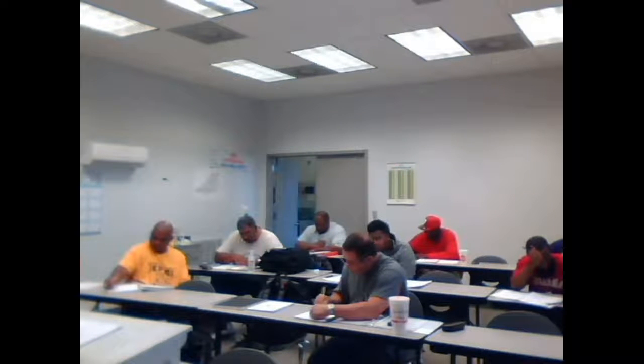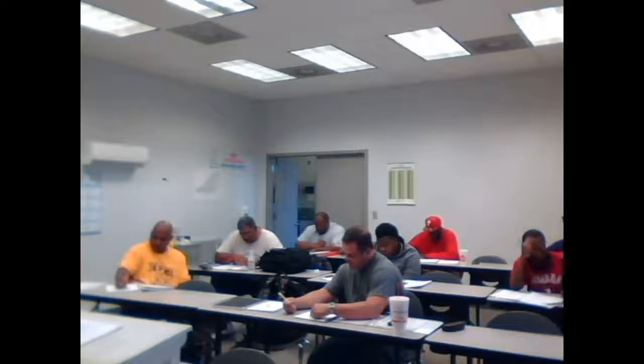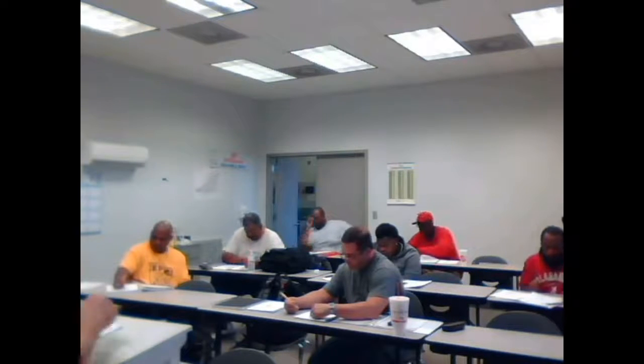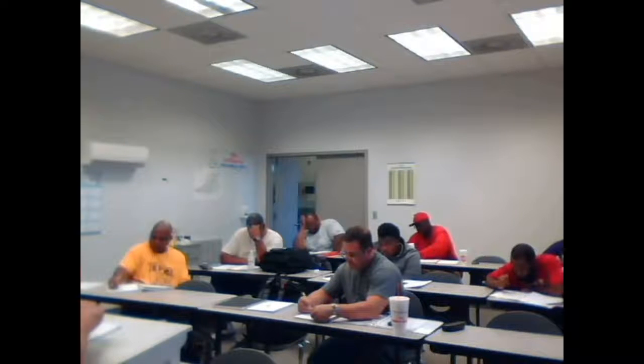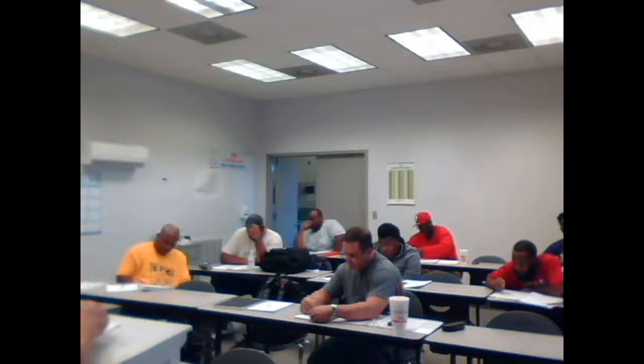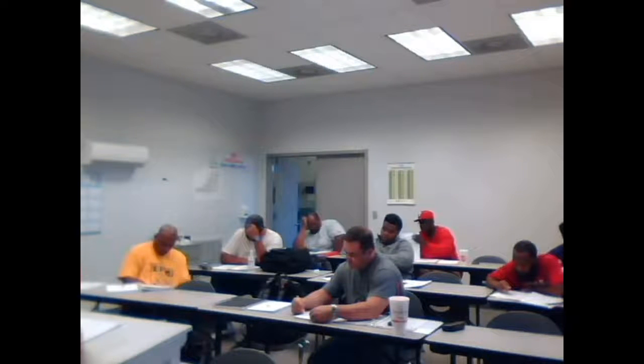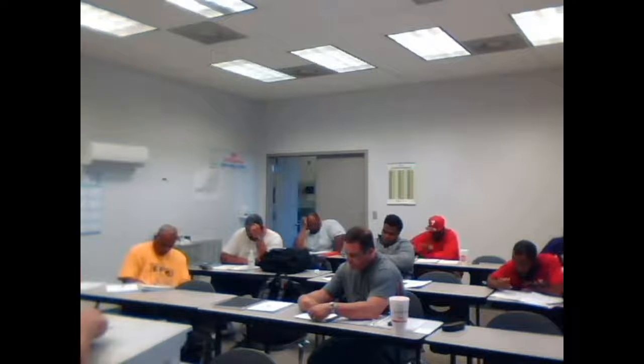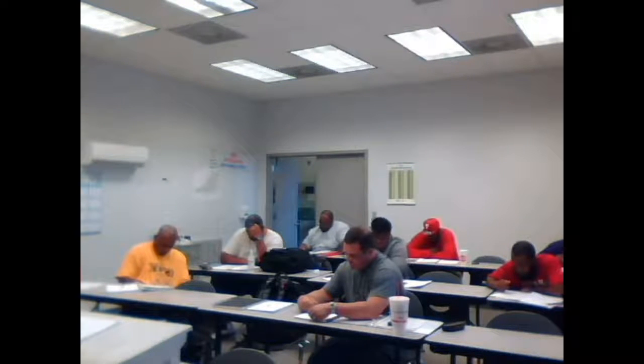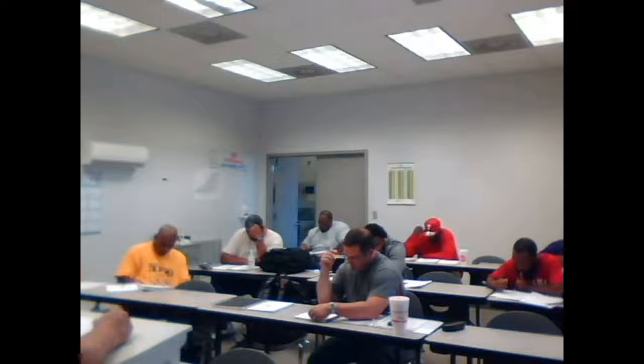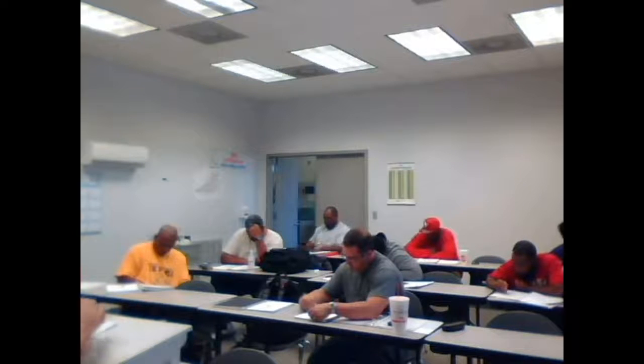All right. Now we're going to go back to our contactor now, y'all. Go back to our contactor. Now, if I look at the top of the schematic, it says L1 feeds the contactor. Right across from it, T1. T1 goes to both number 1 on the compressor and to the condenser fan motor. So coming out of the T1 contactor, I need 2 wires. One goes directly into either side of the condenser. If you look at the condenser fan, it has 2 dots, 2 connection points. So T1 is going to go to one of those.